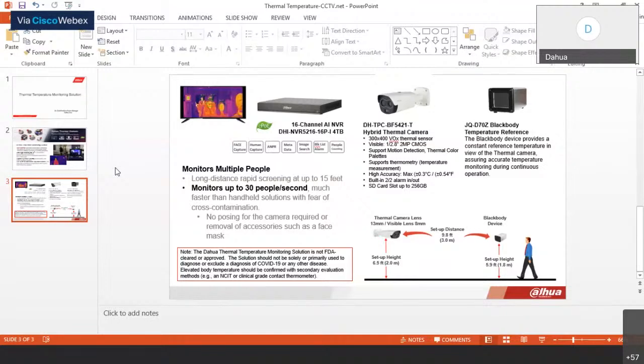When installing the products, the distance and height measurements are very important. Looking at the diagram, the camera height is 6.5 feet, and the black body is lower at 5.9 feet. The thermal camera and the black body have to be facing each other, with a distance of 9.8 feet.